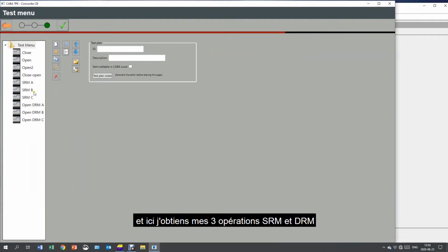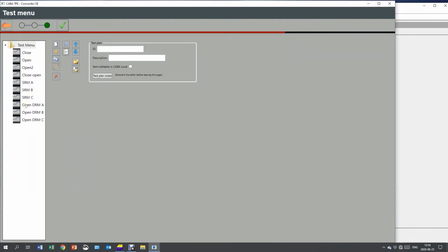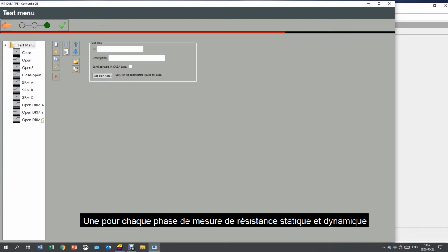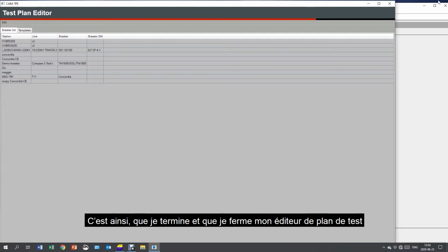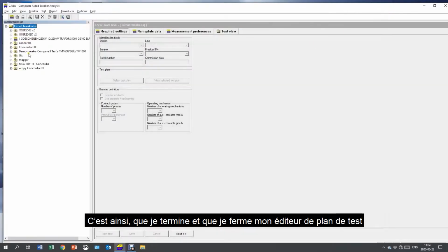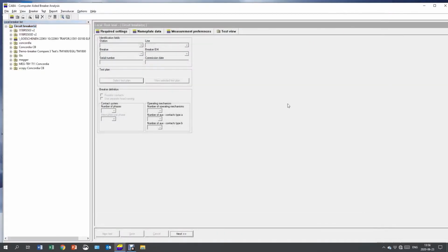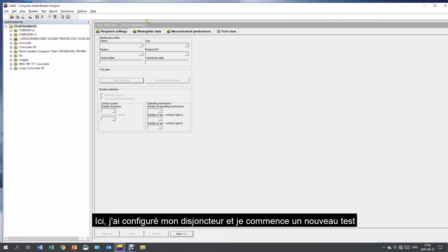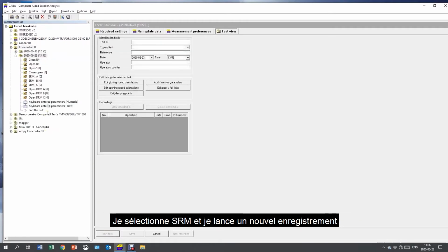And here I get my three operations, SRMs and the DRMs, one for each phase of both static and dynamic resistance measurement. By that, I finish and close my test plan editor. Here I have my circuit breaker set up, and I start with creating a new test. I start with the SRM, and I start a new recording.